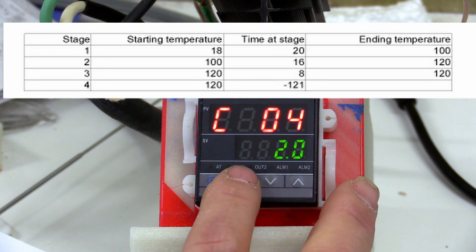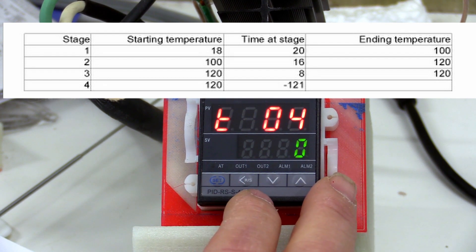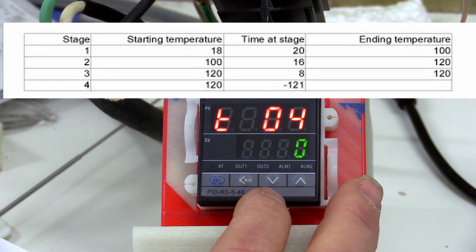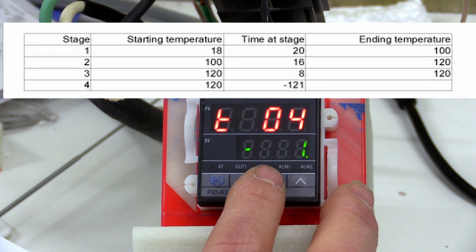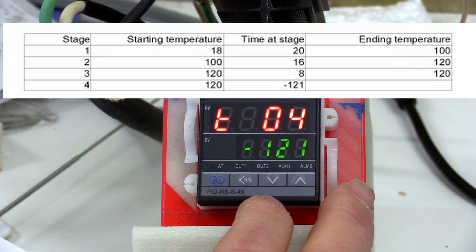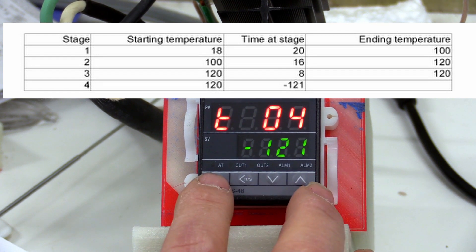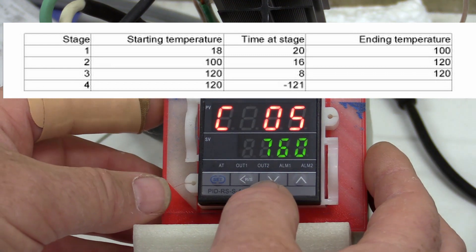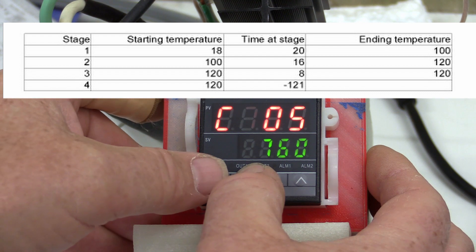Stage 4 is the starting temperature of this stage, which was also the ending temperature of stage 3, or 120 degrees. Hit set. To terminate the program when it's running, enter a time of minus 121. To exit programming, hold the left arrow and the set key at the same time.